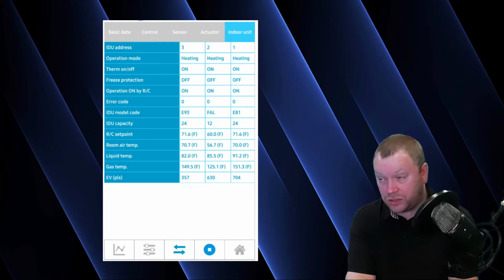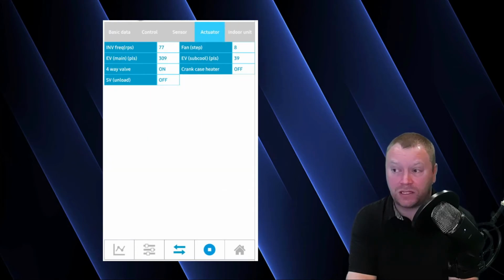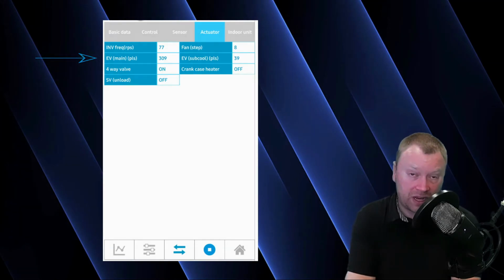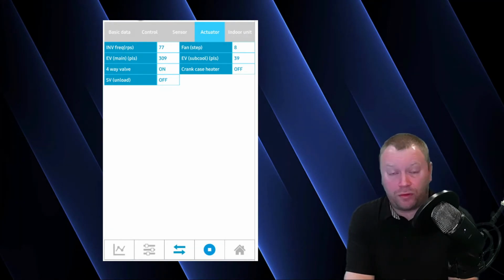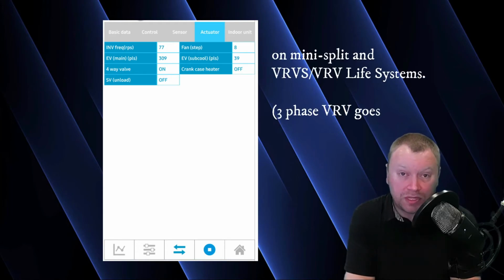So then what I'm going to do is come back to my outdoor unit. Now, when I go back to my outdoor unit, I'm going to go through my outdoor unit electronic expansion valve. So I'm going to go back to my actuator tab, and you can see my outdoor unit expansion valve is at 309 pulses. For reference, your outdoor unit expansion valve has up to 480 positions.